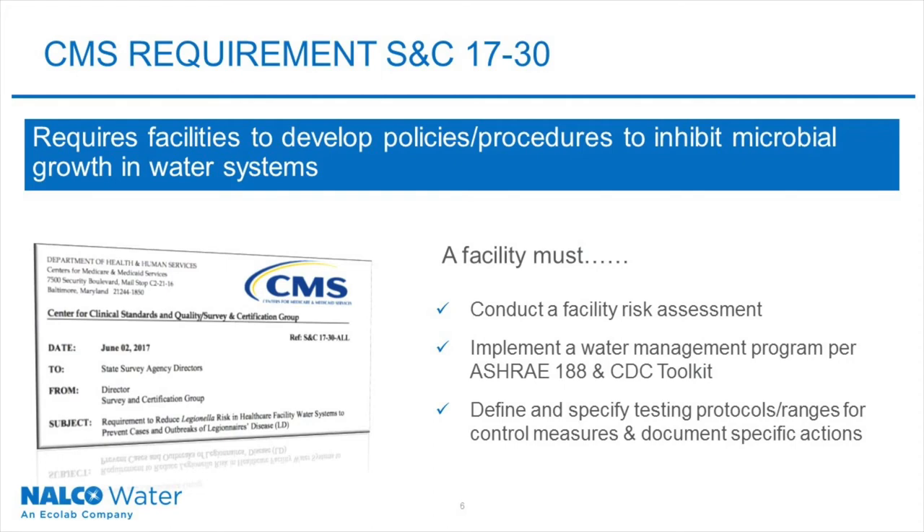S&C 17-30 requires a health care facility to develop policies and procedures to inhibit microbial growth in water systems. There are three things a facility must do. They must conduct a facility risk assessment. They should implement a water management plan considering the ASHRAE standard 188 and CDC toolkit. And lastly, a facility must define and specify protocols and ranges for their control measures and document testing and corrective actions. Documentation is very, very important.